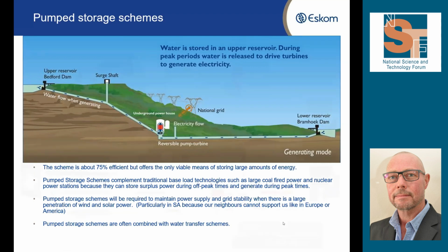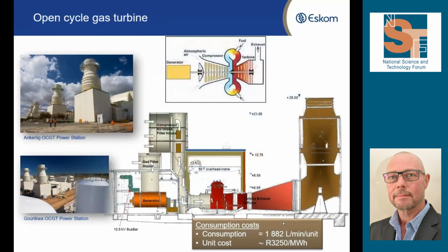The second technology that needs to be understood is our open cycle gas turbines. We have 20 of them in all - Eskom owns 14, and there are 6 privately owned. It's an understatement to say that these things guzzle. The consumption of one diesel generator at full output is almost 1,900 liters of diesel per minute per generator. When we run all 20, you can imagine how much diesel we are using.